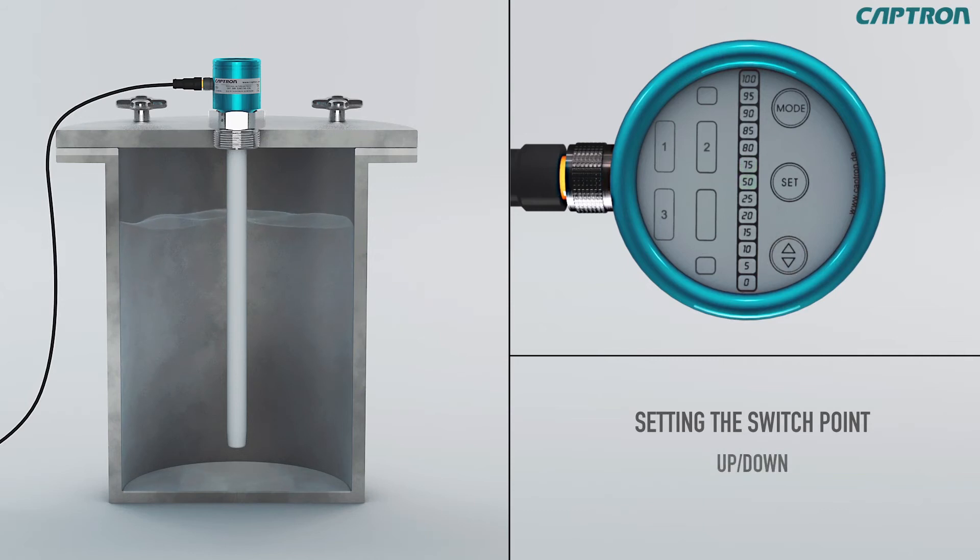When the switch output function is set on NO, the output is on high as soon as the switch point is exceeded. With the option NC, the output is on low when the switch point is exceeded. Confirm your new setting with set.